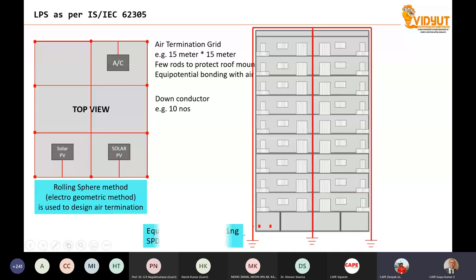So now the second part, as I said, is the down conductor. A number of down conductors are required because the total lightning current shall be divided through different paths in order to reduce the effect of the lightning current. Then at the building, we need to have equipotential bonding. That means the down conductor and the electrical installation bus bars, the earth bus bar, shall be interconnected. And the power lines and data lines, the service lines coming into the building, also shall have surge protective devices. And every down conductor should have an earth electrode.